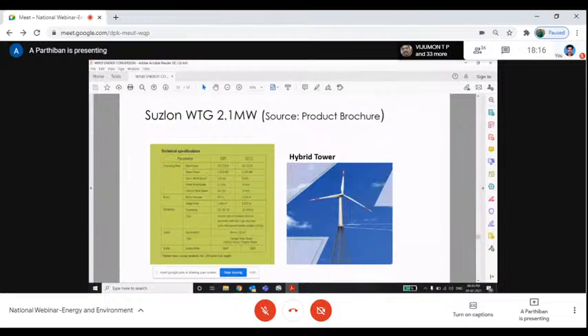This is the technical specification of this particular 2.1 megawatt turbine with S97 and S111 rotor dia. This S97 model is particularly designed for a class 3A wind zone, which has a cut-in wind speed of 3.5, 11 meters per second as the rated wind speed, and a cutout of 20 meters per second. The same 2.1 with the 111 rotor dia starts producing energy at 3 meters per second, and it will achieve 2.1 at 10 meters per second. These are the main technical specifications of the turbine.